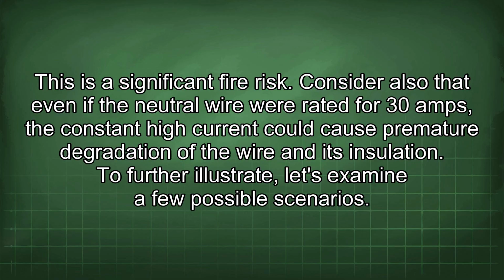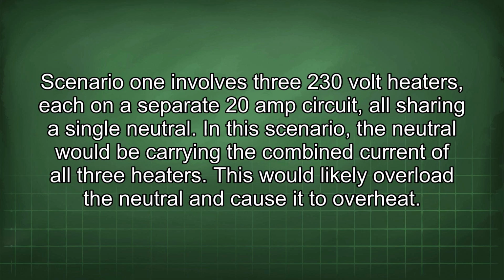To further illustrate, let's examine a few possible scenarios. Scenario 1 involves three 230-volt heaters, each on a separate 20-amp circuit, all sharing a single neutral. In this scenario, the neutral would be carrying the combined current of all three heaters. This would likely overload the neutral and cause it to overheat.